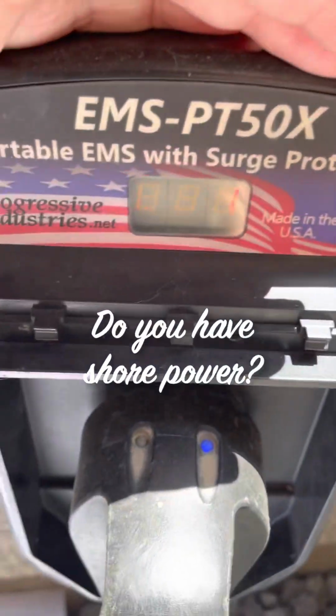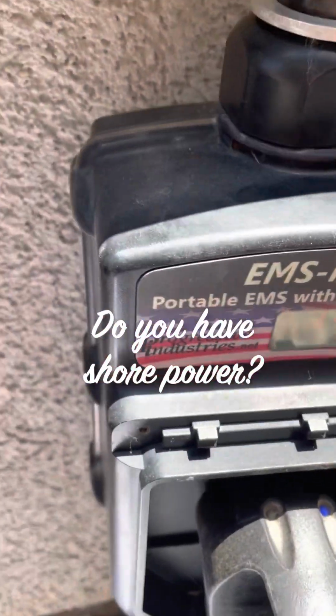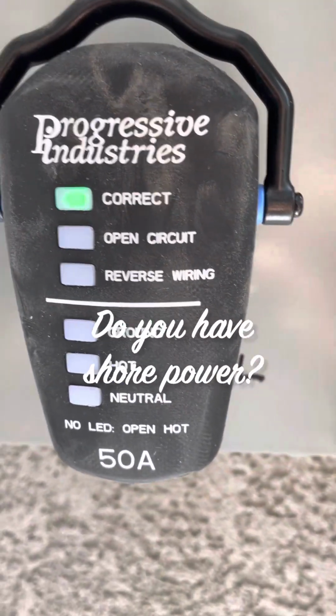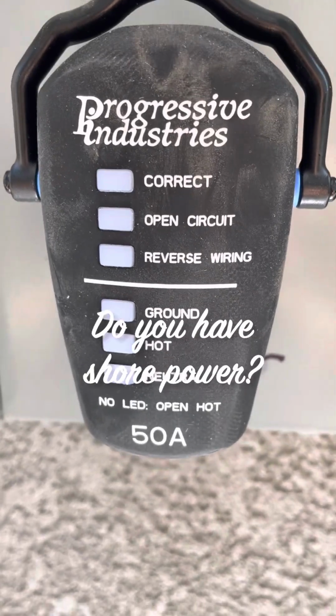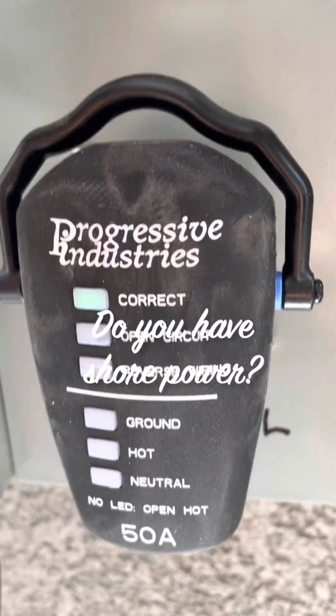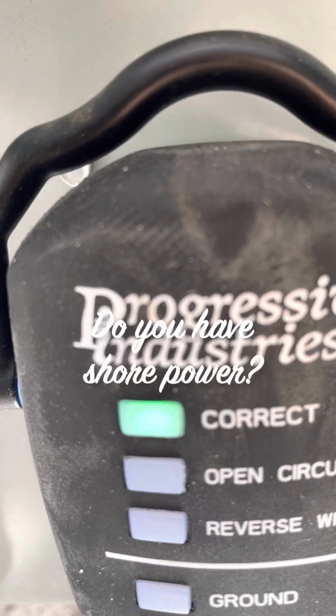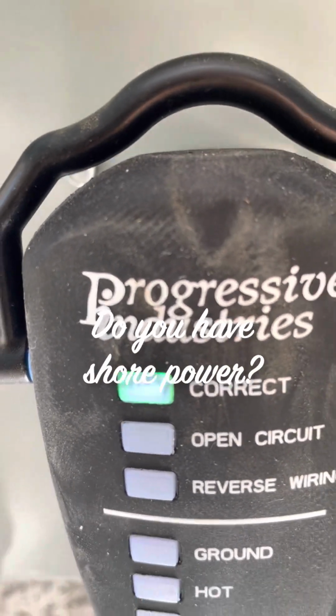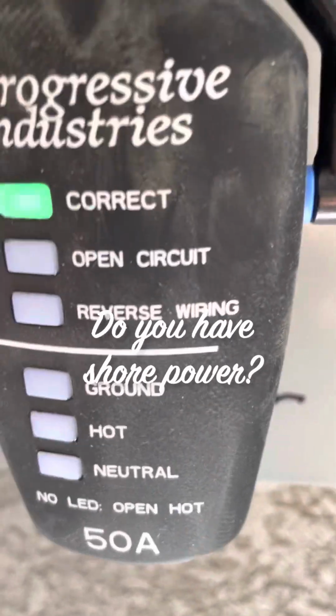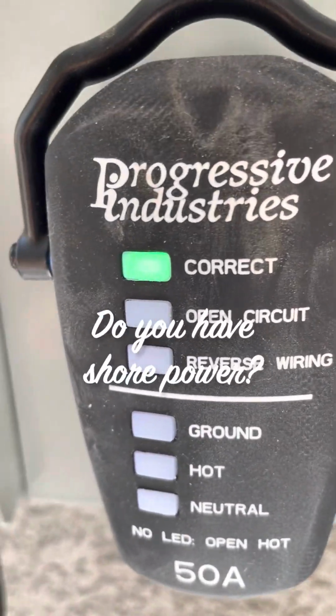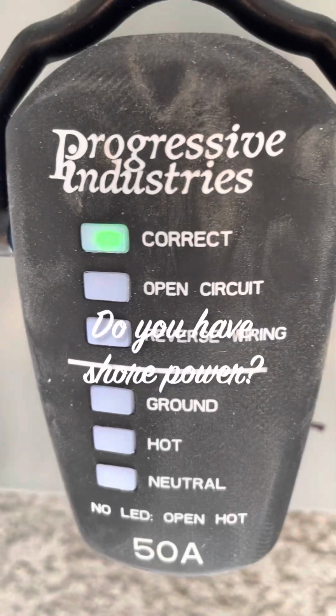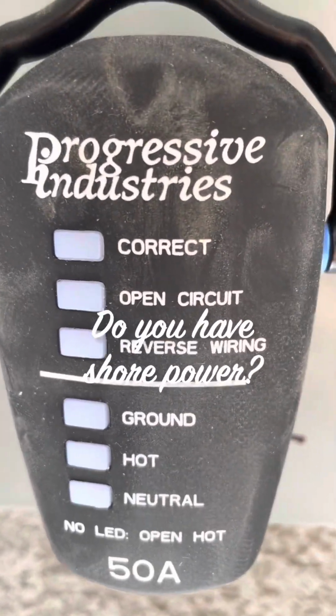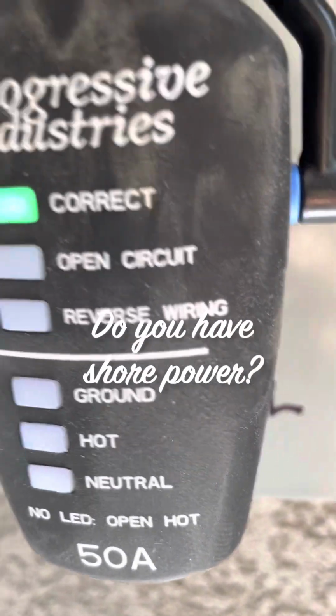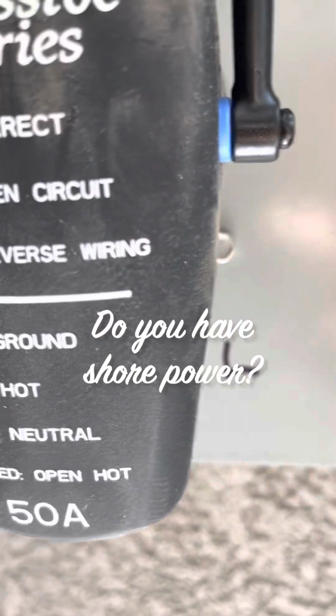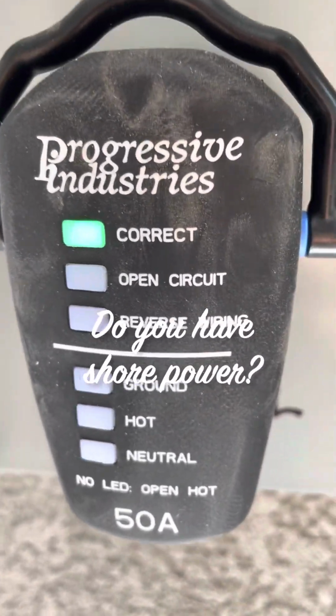If you don't have an EMS, then you can use an outlet tester. This is a 50 amp outlet tester from Progressive. If you look really close, you can see the green light under correct. If there is a problem, one of these other lights would be lit. So what Progressive says is to turn the breaker off, plug in the tester, turn the breaker on, and check that everything is working. If everything is working, then we want to move on and do a little further testing.